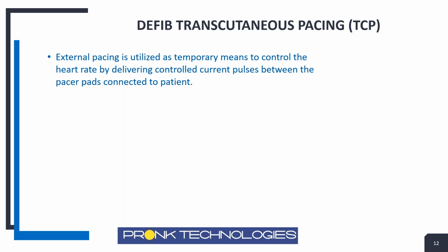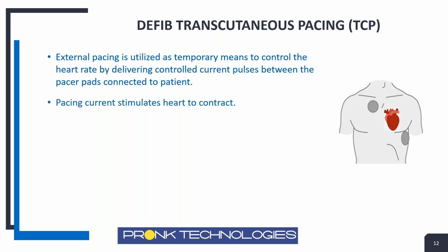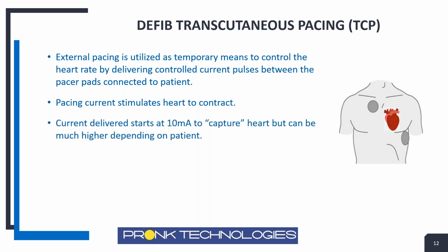So you have transcutaneous pacing. Some defibrillators, particularly hospital grade, hospital level defibrillators, have external pacing, where you sometimes need to control the heart of the patient because the heart rate's not being controlled very well on its own. Using the same pads you would use for defibrillation, you can push DC current across the heart, so to speak, to capture the heartbeat and control the rate. You do this by delivering current across those two pads, positive and minus, to capture it.